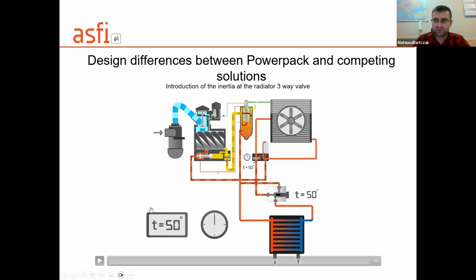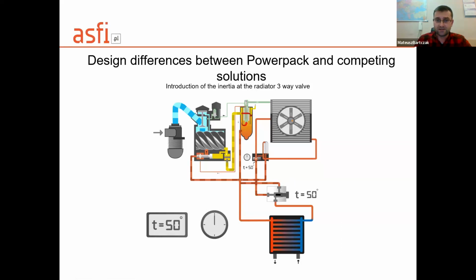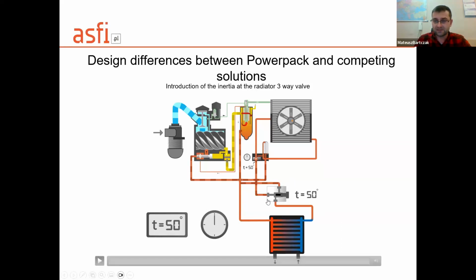Here we have a screen of the controller, a compressor. We can watch here the increasing temperature when the compressor is on load. Heat exchanger and of course the valve at this heat exchanger. The insert of this valve is 55. Here is a three-way valve with integrated filter, the standard, which is built into the compressor. Its insert thermostat is 75. So what happened here?